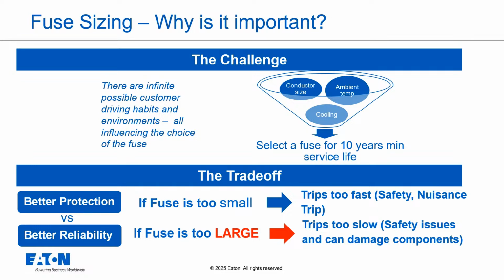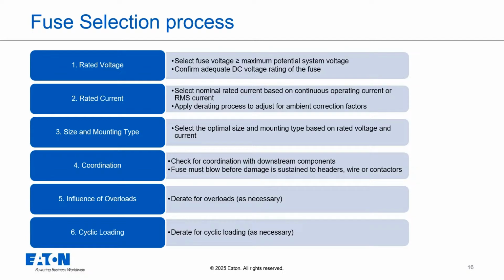Environmental factors like cooling, conductor size, and ambient temp heavily influence this. Let's walk through a typical process for selecting an EV fuse. Step 1, rated voltage. You need to select a fuse voltage rating that is greater than or equal to the maximum potential system voltage, and specifically confirm it has an adequate DC voltage rating.